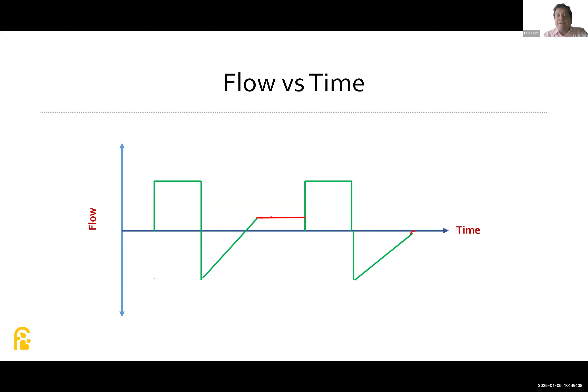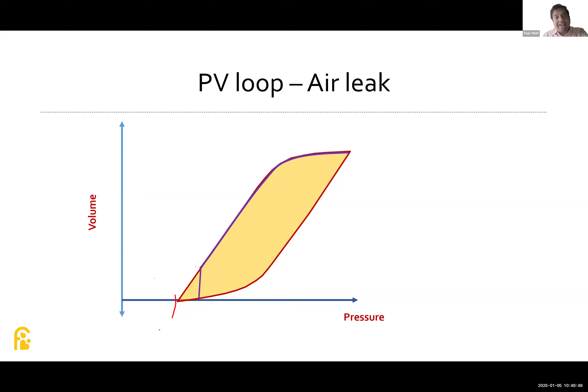PV loop, how it will appear? Initial PV loop, you know that this is how it will appear. So initially the inspiration is going very nicely, but during expiration, just follow that purple line. It is not coming back to the initial point. So that means that much volume is getting lost. So this is all your air leak once again. The volume loss which has happened.